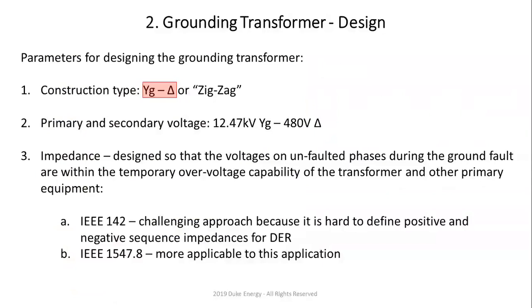Third one is impedance. Impedance can be designed a couple of different ways: IEEE 142 or IEEE 1547.8, which is more applicable to this application and is pretty much the way that I have done it, right? One thing you have to understand for impedance is that the X/R ratio of the transformer has to be greater than 4 to provide for solid grounding. I'm going to show you later why this becomes a little more challenging. If you look at different transformers, you can see that probably over 400 kVA you get an X/R ratio over 4. The particular transformer in our case is 500 kVA, with an X/R ratio of 5.09.